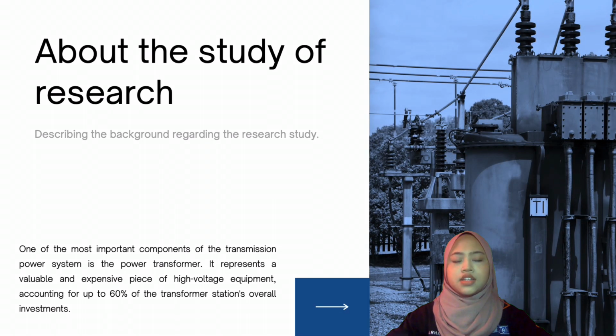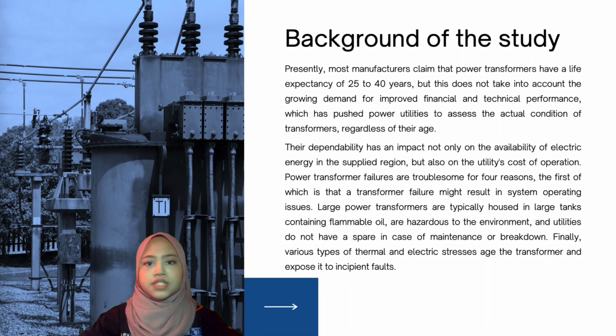About the study of research, one of the most important components of the transmission power system is the power transformer. It represents a valuable and expensive piece of high voltage equipment, accounting for up to 60% of the transformer station's overall investments. Presently, most manufacturers claim that power transformers have a life expectancy of 25 to 40 years, but this does not take into account the growing demand for improved financial and technical performance, which has pushed power utilities to assess the actual condition of transformers regardless of their age.